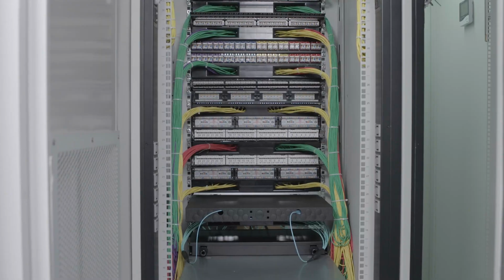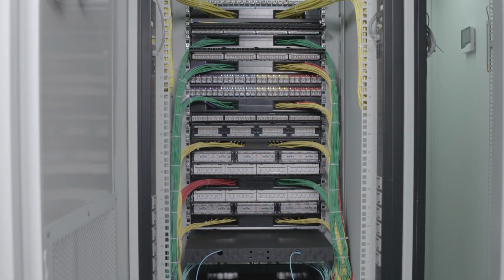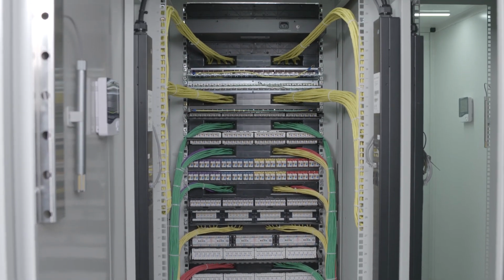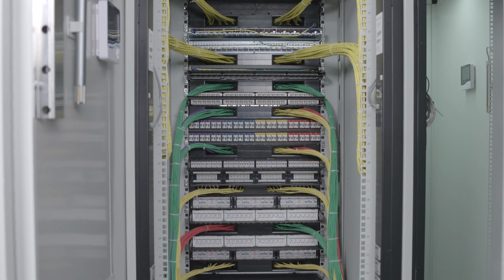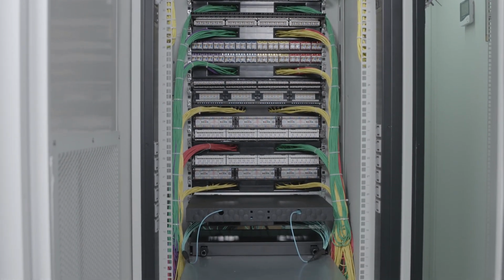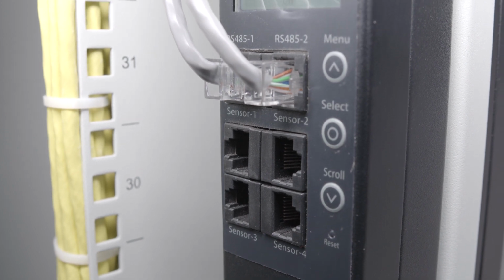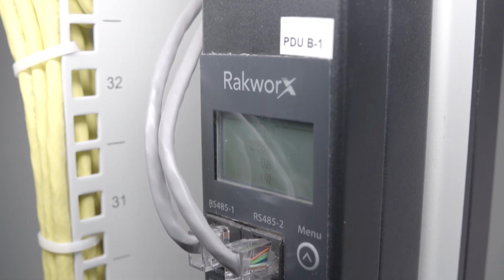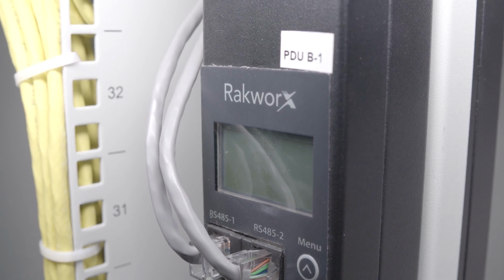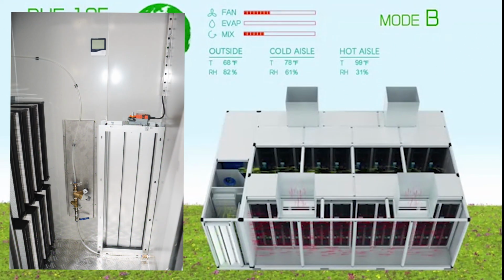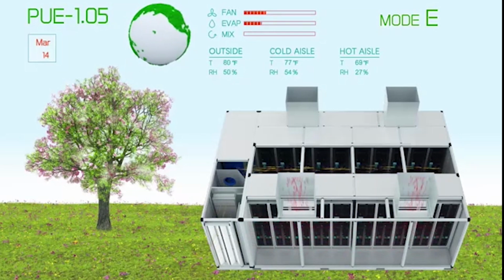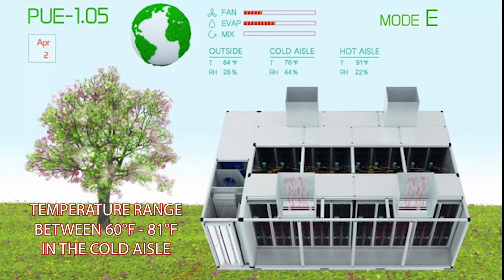All you have to do is connect your servers and battery backups, making this as close to plug and play as possible. Once everything is installed, each rack's components are plugged into our intelligent power distribution units. We install 2 PDUs per rack to ensure there is a redundancy in case a server overheats or the power supply fails, and that everything is operating at peak performance. When the MDC is in use, the hottest air escapes through the ceiling dampers while the rest is forced by the MDC's fans through the damper in the wall back into the intake room to be cooled further. This keeps the MDC operating to ASHRAE standards of between 60 and 81 degrees in the cold aisle.